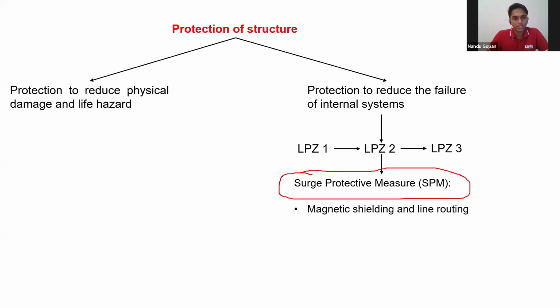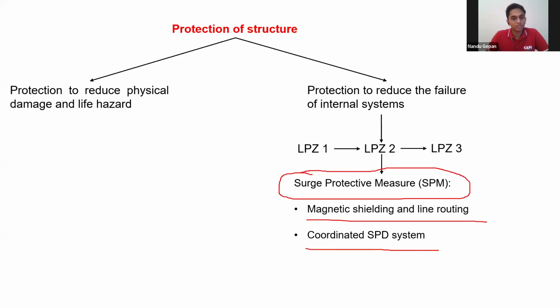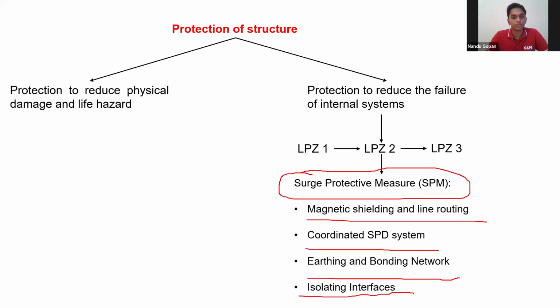Surge protective measure is classified into: first, magnetic shielding and line routing; next, coordinated SPD system; next, earthing and bonding networks; and next, isolating interfaces. To achieve good surge protective measure in your building, you need all 4 of these - similar to how, for a good lightning protection system in external LPS part 3, you need air termination, down conductor, earth termination system, and equipotential bonding.